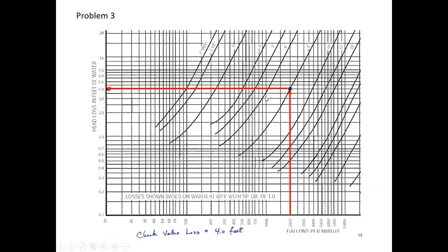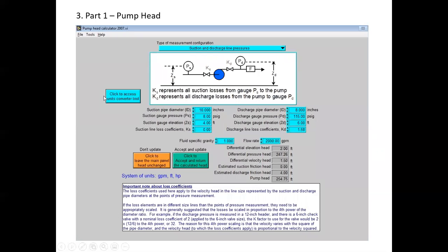Okay, so we're at 2,000, and these are the curves that came from the check valve manufacturer. This one predicts for the given size, and we have an 8-inch check valve. So at 2,000, we read up and over, and that says we're going to have 4 feet of loss. So this doesn't give us a K, this gives us an actual feet of loss across the valve. So we have to play with this a little bit differently.